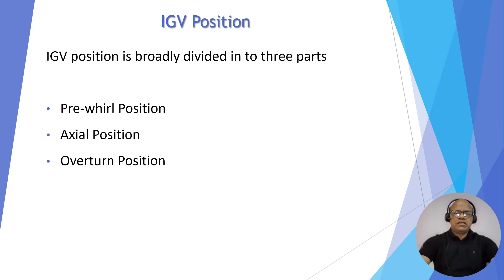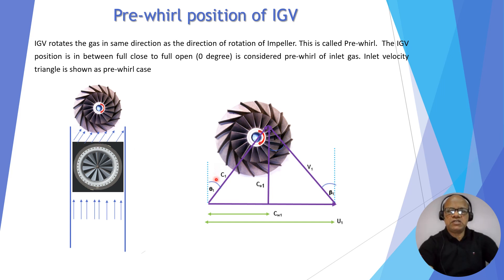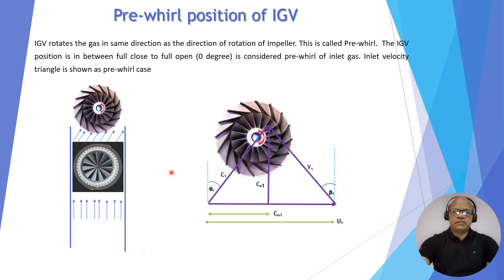IGV position is broadly divided into three parts: pre-whirl position, axial position, and overturn position. In the case of IGV in pre-whirl condition, the gas is turned in the same direction as the direction of rotation of the impeller. You can see the velocity triangle: C1, U1, V1, whirl component CW1, and axial component CA1. This is the pre-whirl inlet velocity triangle. The range from full close to full open position in between is called the pre-whirl position of IGV.